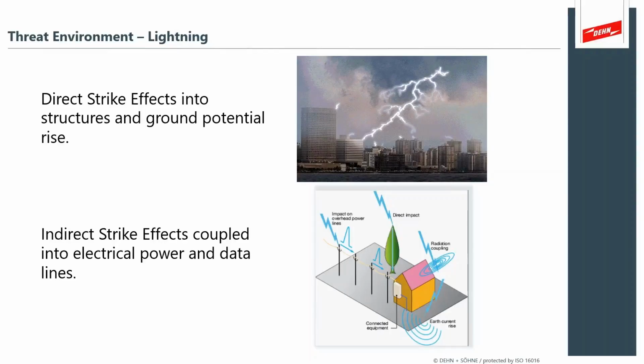So direct strike, of course, that's the big kahuna, as it were, where the charge moves through the atmosphere. It strikes from 10 miles away, moves horizontally, moves sideways, vertically, and it attaches, and you have the discharge event. That's the full lightning strike effect. And that is, of course, very energetic, and there's lots of descriptions in the standards that tell you how much current, where does the current go, what should you expect to see.